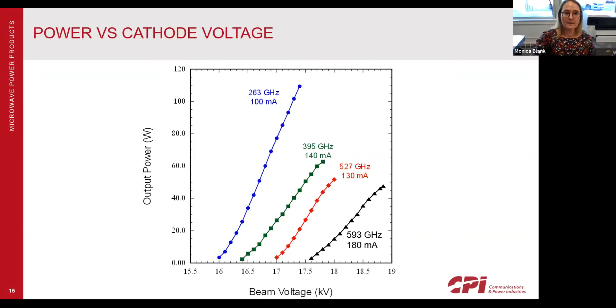And you can also see that even though I bragged that the gyrotron can do whatever frequency, whatever power it wants, it is actually a little bit harder to make power at a given cathode voltage and beam current. It's harder to make power at the higher frequencies. And that's because of a lot of effects: at higher frequencies, mechanical alignment is getting more important. Also, ohmic losses in our cavity are going up at higher frequencies. So the gyrotron has the ability to make whatever power you want, at least for spectroscopy, but you might need a bigger power supply. All 4 of these gyrotrons use the exact same power supply. So we didn't have any more input power available, and that's why we made a little bit less power at 527 and 593.